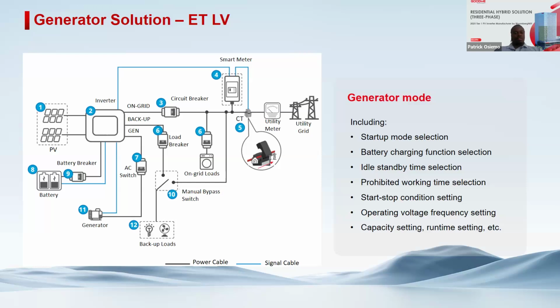Now, it does not end there. Before it even switches on the diesel generator, you can choose what times during the day or night that the ETLV can allow the generator to switch on, because you don't want noise at night or maybe noise in the early morning because of the diesel generator sound. You can also choose the idle stand time duration that the generator requires before it fully gets powered, gets a complete power from the output.